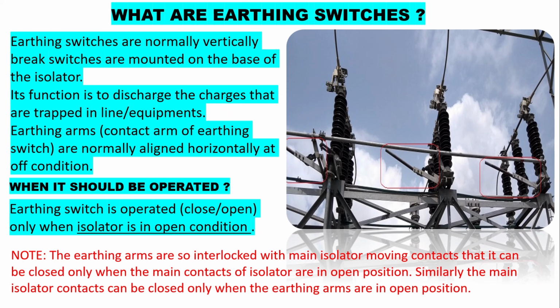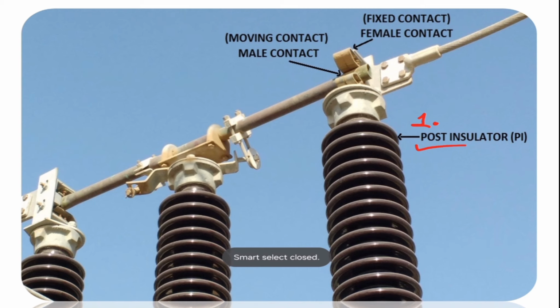Let us try to understand in more detail. An isolator consists of three main parts. First is the post insulator, also called PI. Depending upon the voltage class level, the PI size and dimensions increase or decrease. Second is the moving contact, also called the male contact. And third is the fixed contact, also called the female contact. Depending upon the voltage class level, the fixed and moving contacts vary in design and dimensions.